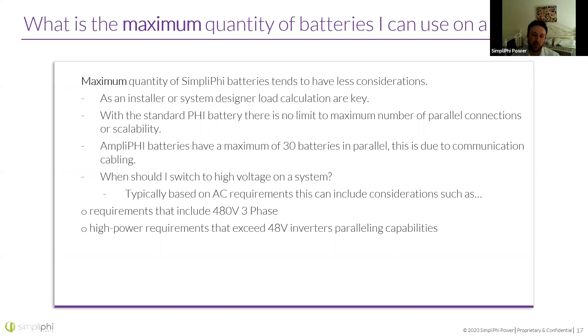This question comes up a lot, kind of piggybacked off this main question: when should I switch to the high voltage from your standard, let's say 48 volt product? It's really mostly going to be based on your AC requirements. So let's say your requirement is 480 volt 3-phase for a project, then it's definitely going to make sense to go ahead and switch to a high voltage product. It's going to pair with the inverters that you need to get that 480 volt 3-phase, and it's going to be able to handle the power that's really required in those situations. And if a power requirement exceeds a 48-volt inverter's paralleling capabilities, this is often a good time to switch over to our high voltage as well.